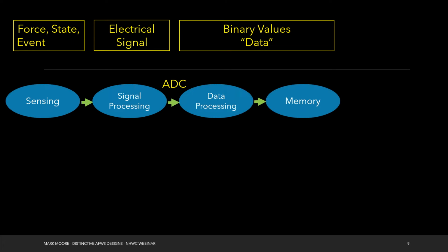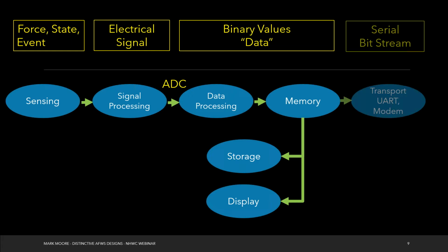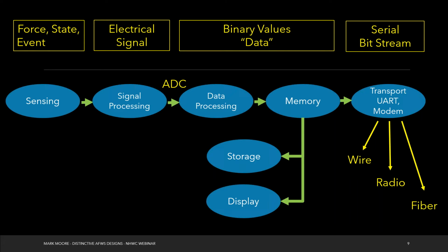So we have the signal that's maybe 0 to 5 volts, and we turn it back into something meaningful, like 10 feet, 15 feet of water. We've now done data processing, and then we store it locally. Maybe we display it, or we transport it away. We send it through some sort of wire. Maybe it's a gauge on a dam that's connected straight to the network. Or oftentimes we're talking about radios. So we've got an ALERT2 site set up to transmit this, or it's cell radio, or any type of way to send it, or even a fiber optic line. So there are various ways that we can actually send this information.